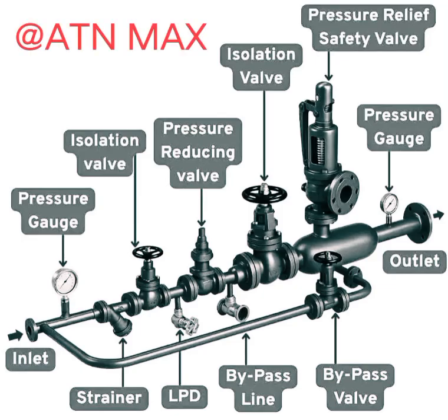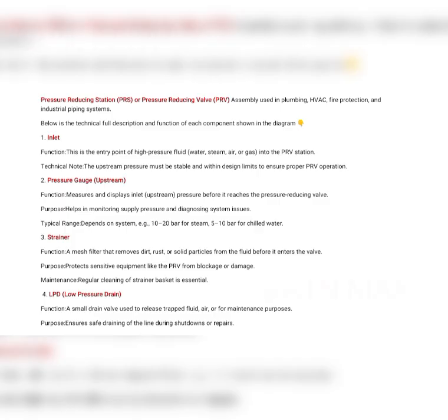Pressure reducing station, PRS, or pressure reducing valve, PRV, assembly used in plumbing, HVAC, fire protection, and industrial piping systems. Below is the technical full description and function of each component shown in the diagram. 1. Inlet. Function: this is the entry point of high-pressure fluid, water, steam, air, or gas, into the PRV station.